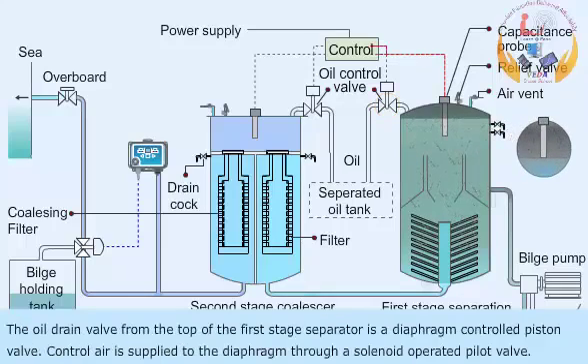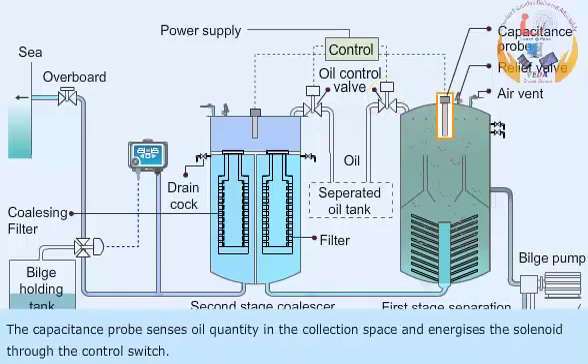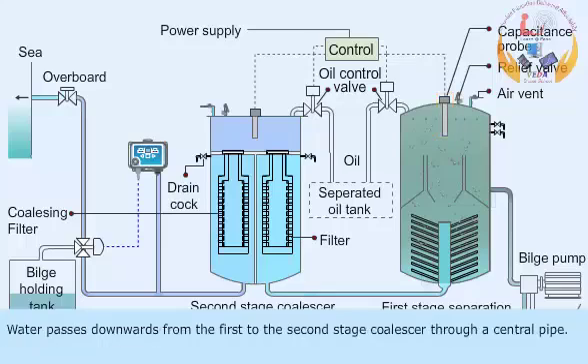The oil drain valve from the top of the first stage separator is a diaphragm controlled piston valve. Control air is supplied to the diaphragm through a solenoid operated pilot valve. The capacitance probe senses oil quantity in the collection space and energizes the solenoid through the control switch.